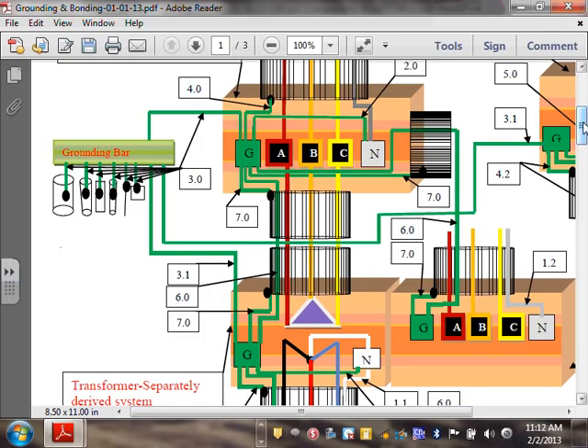The easiest way to create another neutral, if you already have a neutral, is if you have another transformer, right? Here's a transformer, a delta, or it could be a Y, by the way, but typically delta transformer, and Y. So now I created another neutral. I call it white. That's a white neutral. That's my 208/120, typically industry standard color code, right? And I pulled the 208/120 black, red, blue, and I colored them because they're 208/120.